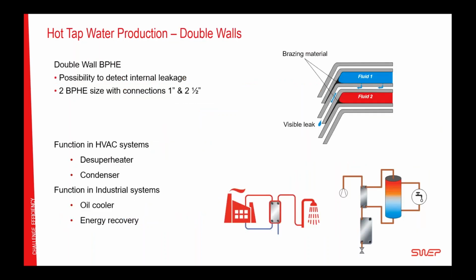But let's look at one of the more interesting ones, and that's the double wall. And why do you need a double wall, and what is a double wall? Let's start with that question. So a double wall is the cold side and the hot side that are close to each other, but there's something in between. There is a very thin open channel between them. That's the double wall. Why do you want to do this? This reduces the energy efficiency of a heat exchanger by about 25%, something like that. So you lose that efficiency.